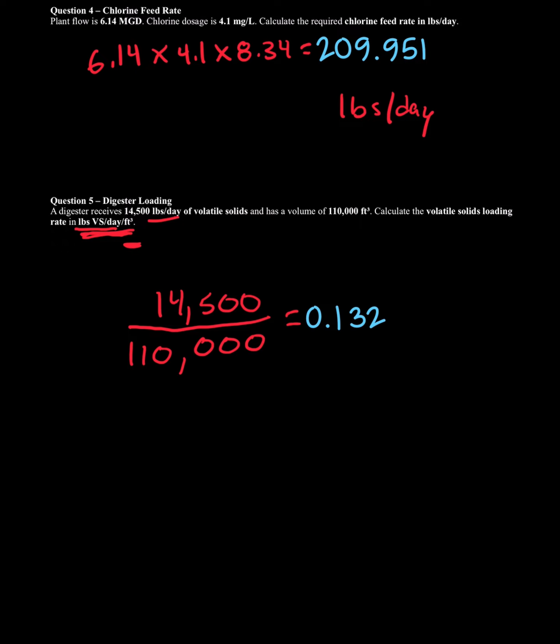And that is going to be a volatile solids loading rate of 0.132 pounds of VS per day per cubic foot.